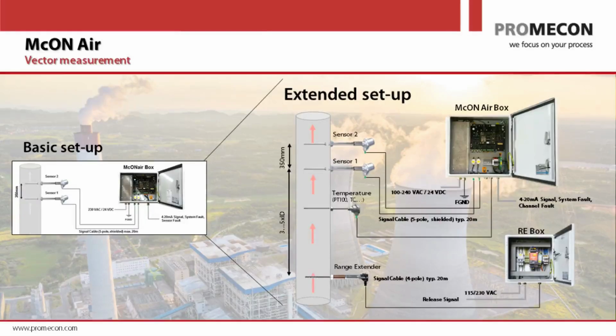The power supply is usually anything between 65 and 240 volts AC, 50 hertz, 60 hertz, or you can also have 24 volt DC supply. That's up to the user to decide. And then that's basically the whole setup. So for every measurement location, you get a 4 to 20 milliamp signal for the velocity that you then scale and compensate for the individual parameters on the duct. And then you have error levels below 4 milliamps, starting from 3.6 milliamps down. You can have several error level indications: sensor cable broken, sensor reading not valid. 0 milliamp, of course, is then power failure. So these sort of error levels you can then also take into your DCS and use for controls.